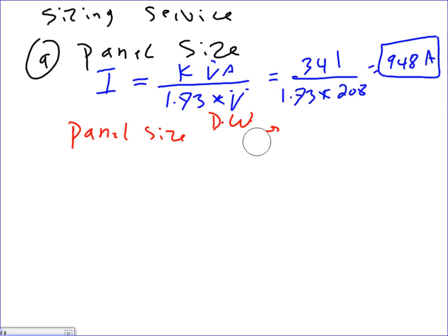All right, let's go one more time. 3-13. Everybody knows what 3-13 is in the DeWalt? If you go to switchboards or switchgear, what's my next standard? Look at the three-phase section. Do I have 1,000? 1,200. Now I want to warn you, guys, this is the bus inside the panel, not the overcurrent device.